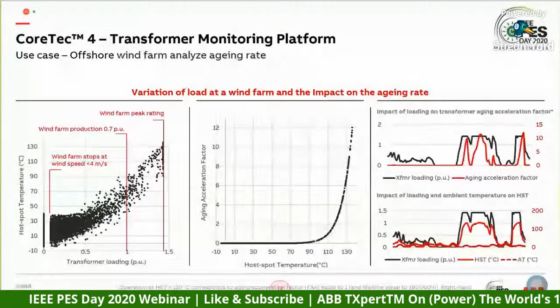I will also present a use case where we had an offshore wind farm that ordered a transformer with a load profile representing around 70% of peak production rating. Even if you look to the left, most of the production happens when the transformer is at less than 60% of load. But when the wind picks up, the transformer is overloaded. This overloading increases the hotspot temperature, which in turn increases the aging acceleration factor.